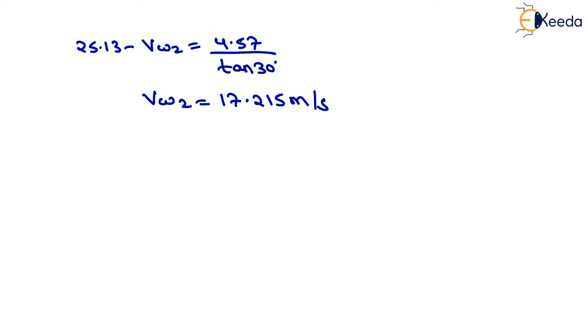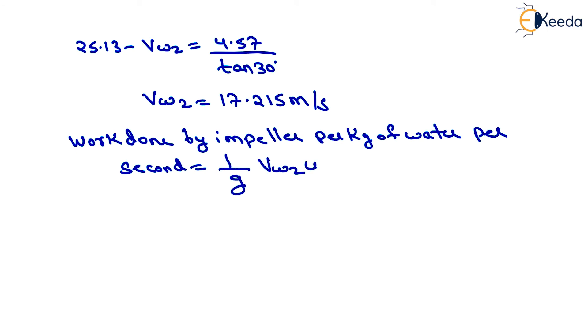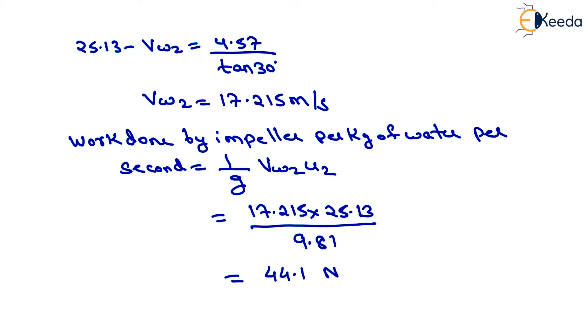Work done by the impeller per unit weight of water is given by (1/g) times vw2 times u2. Putting in the values: 17.215 times 25.13 divided by 9.81, we get the value equals 44.1 Newton-meters per Newton. That is the work done by the impeller per unit weight of water.